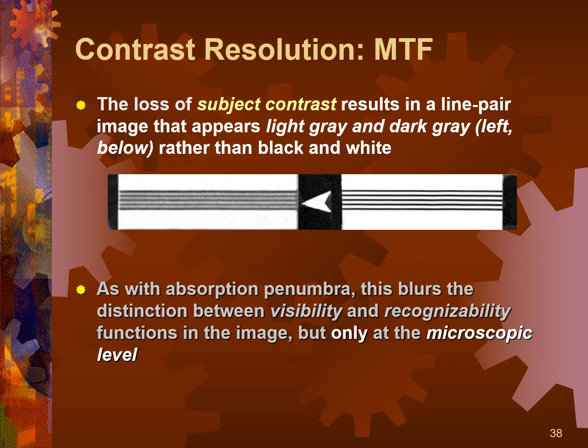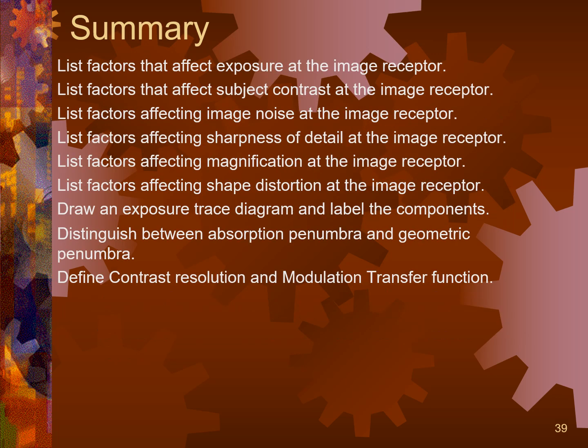So that's the loss. That's why these line pairs, if you're being honest with yourself, that's not white, that's gray. We're already seeing the penumbra bleeding into the inner space, or bleeding into the lead strip, so to speak. Whereas on this other side, we still have sharp edges. All right, that was the end of that.